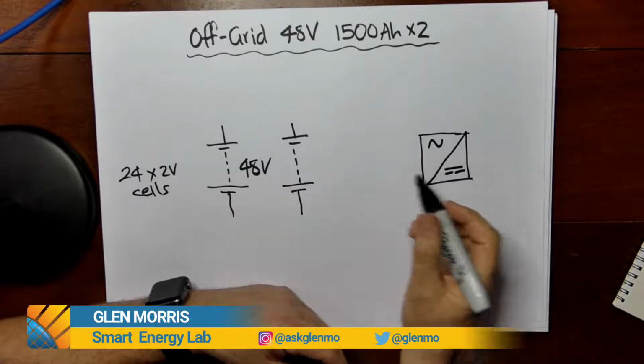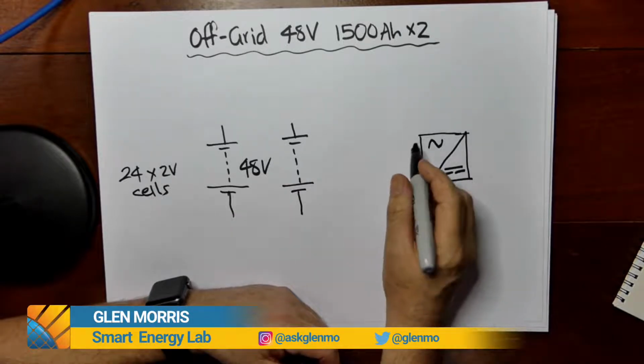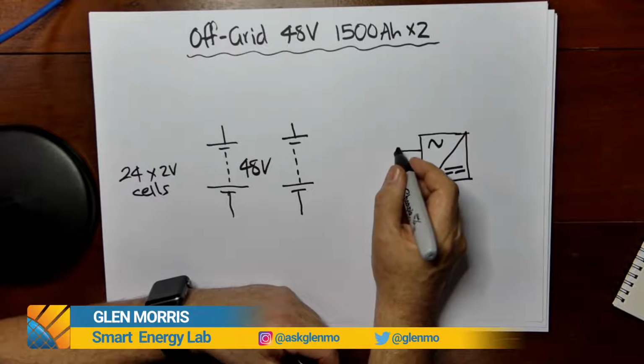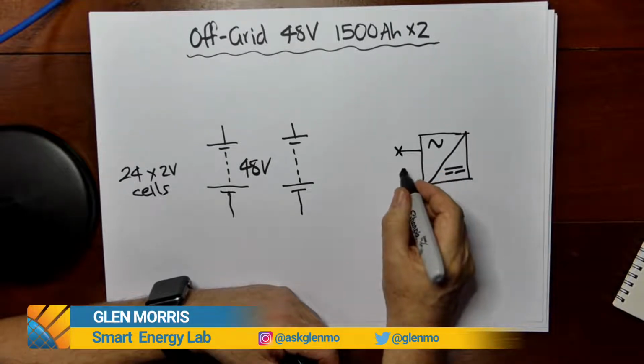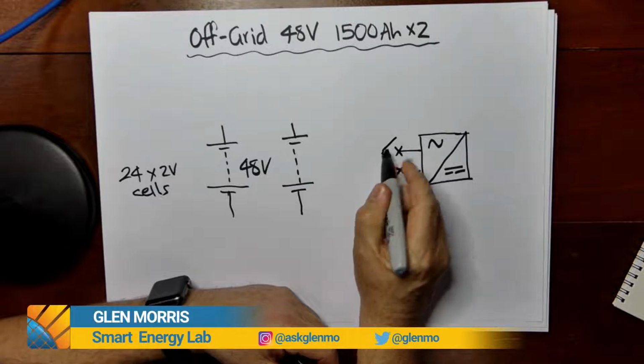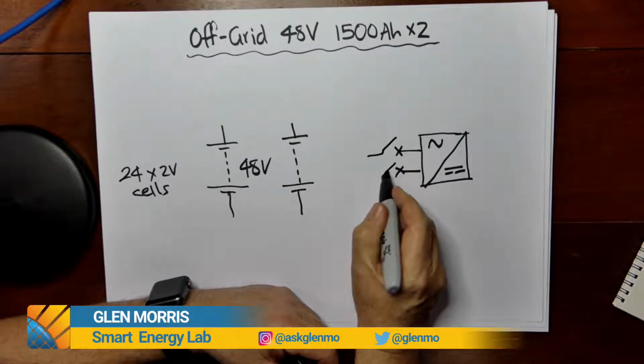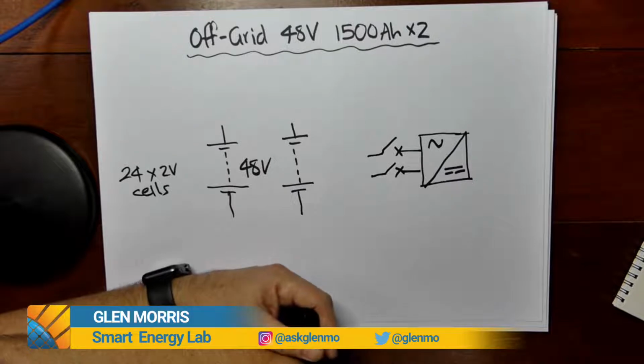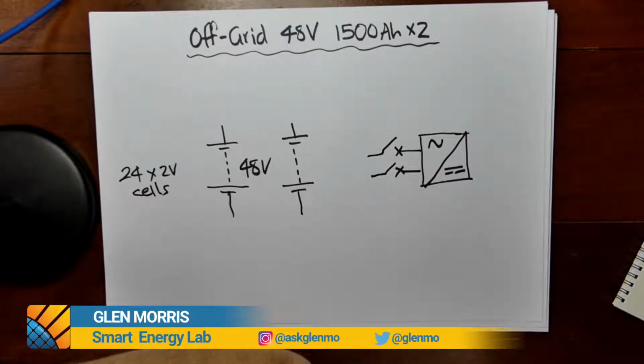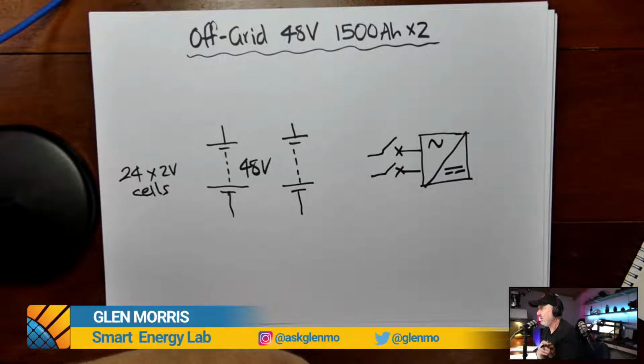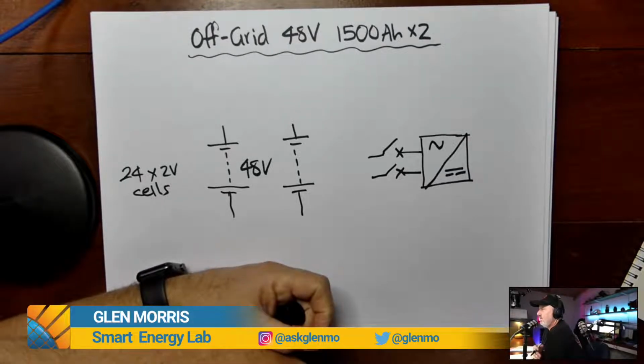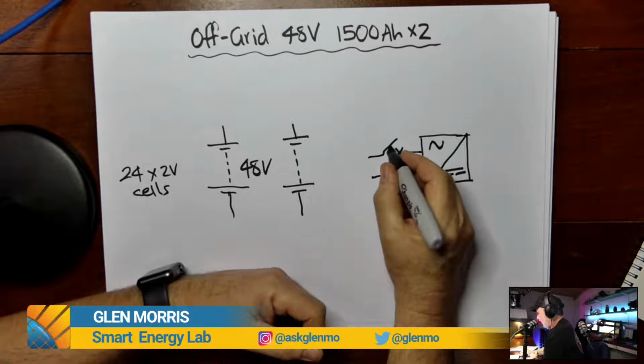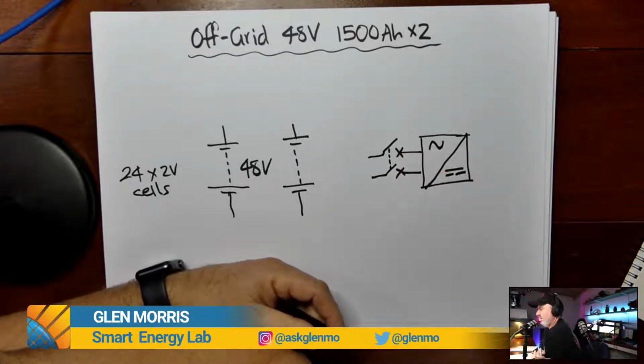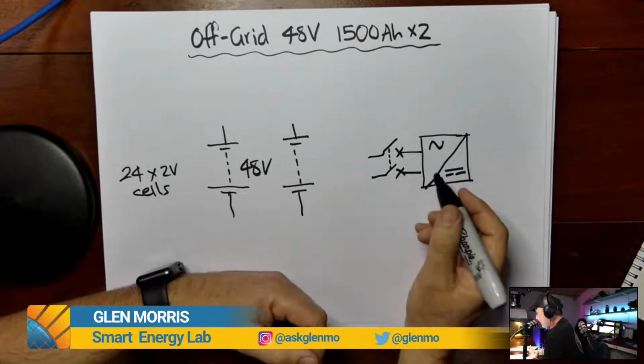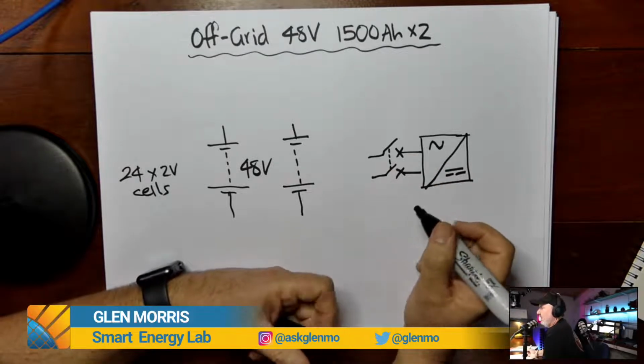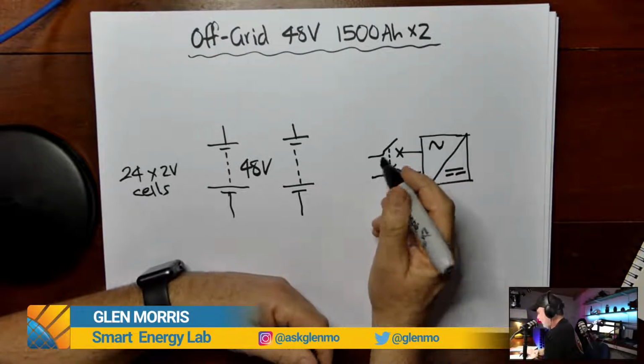Now, we're going to need some isolation on this system. So at the inverter, we're going to need to be able to isolate this system here. Now here's the first change from the old standard. You used to be able to put in separate overcurrent protection and isolation devices, but actually now you have to have them ganged together. So you can't have a separate fuse on the positive and a fuse on the negative, for instance. So here we've got a ganged combined overcurrent and isolation device.